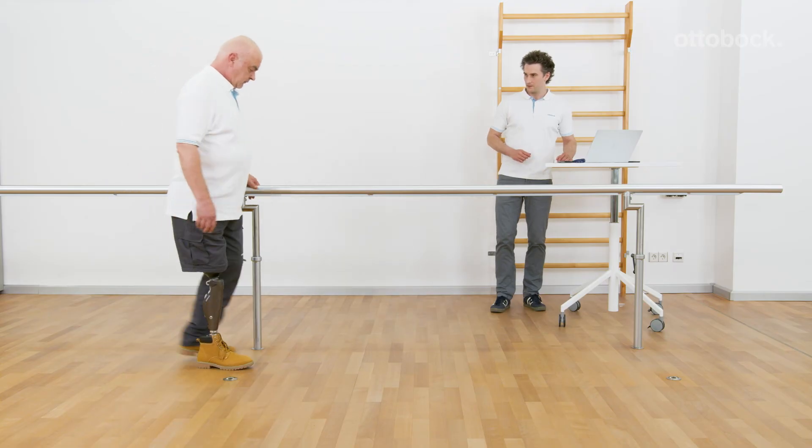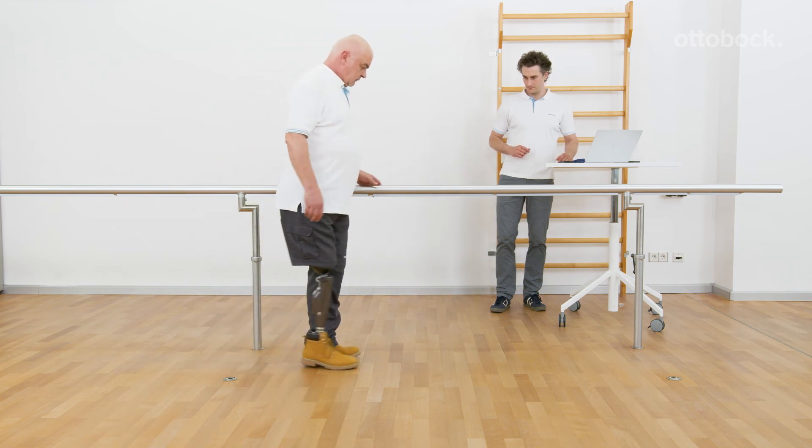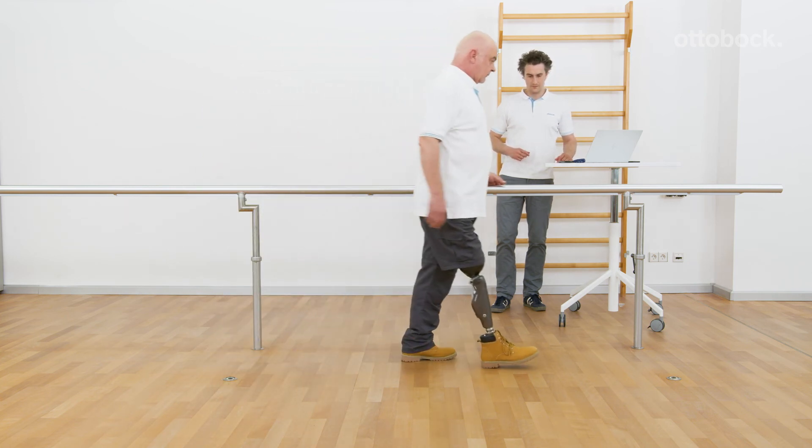C-Leg is not of the latest generation. Feedback function is not activated. Alignment and/or adjustment parameters of the knee joint are not set correctly. The user is walking too passively and is not reaching the required criteria for stance release.